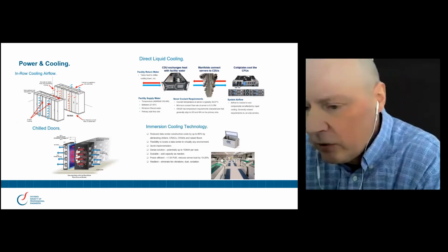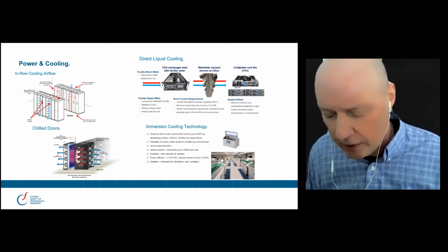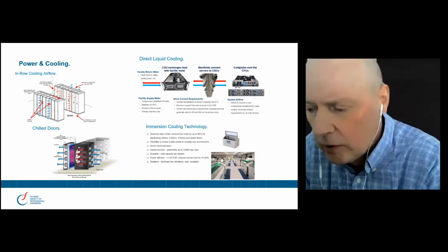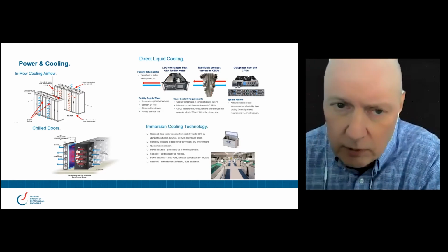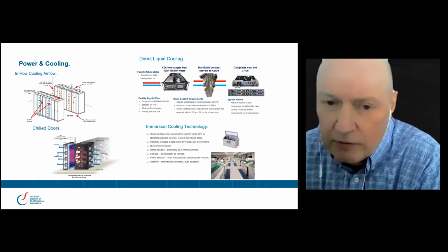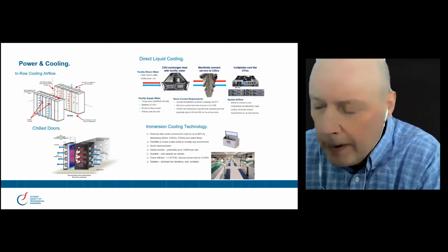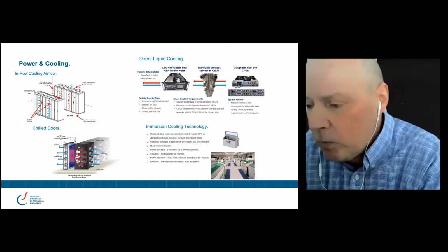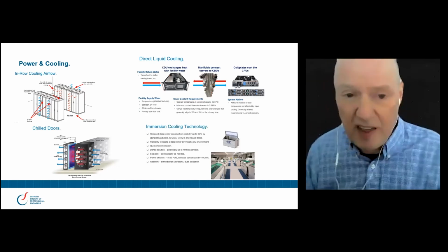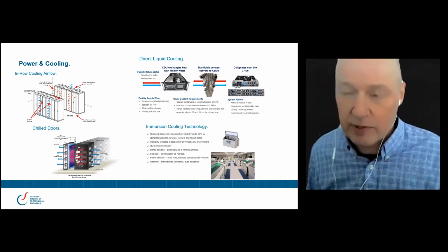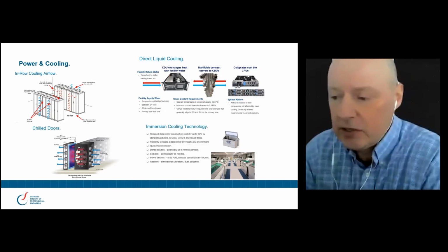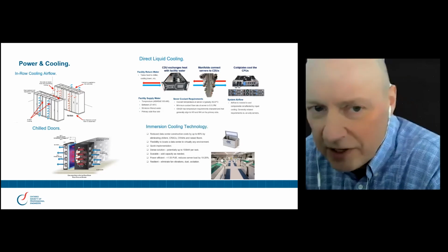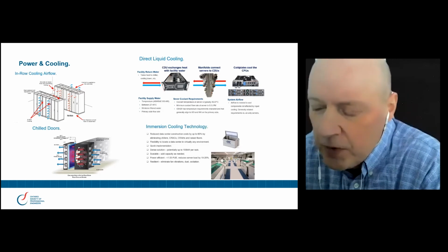Then there's immersion cooling, which is a little bit more exotic, but it's gaining more and more interest over time. I know our company, amongst others, is investing in immersion cooling. Basically, it's a big freezer chest full of liquid, and you take the server and immerse it directly into the coolant, right into that tank. When you do that, you have to remove the fans. You can't have hard drives, because they're mechanical. And as you can imagine, you don't just take your regular old server and dunk it in there. You have to have help to make sure that your server is ready for this. Then you put it into that tank.